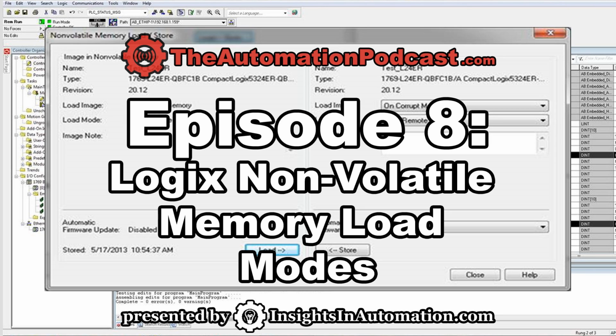instead of leaving the memory blank, it loads a default program. Once that default program has been loaded, if you put in a memory card that says load on corrupt memory, your processor's never going to load from that card because memory's not corrupt. It has a default program in it. So the way we test this, and the way you get around this if you powered up your PLC before putting your non-volatile memory in, is to erase the processor's memory and power it up with the non-volatile memory installed.